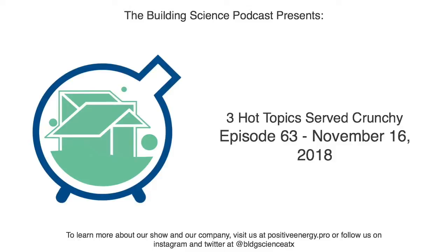Good. So they have the adjusted SRE and then the adjusted TRE, the total recovery efficiency. Right. Unfortunately, the total combined is the enthalpy efficiency, the combination of moisture transfer and sensible heat transfer. Some of the manufacturers do publish their moisture transfer in the winter condition, and a couple publish it for both the winter and summer conditions. Not enough. It's hard to find those specs. But if they do publish the summer moisture transfer and you know the total enthalpy transfer, you can do the calculations on the back end to work out what the sensible heat transfer has to be to arrive at that total enthalpy percentage. It's a bit of a pain, and it would be nice if they just published it. I wonder why they don't. Maybe trade secrets are hidden in there somehow.